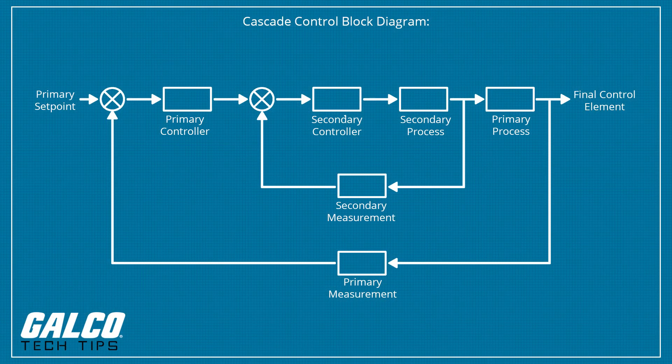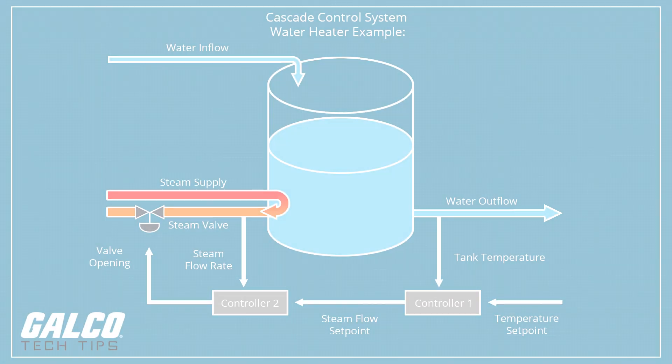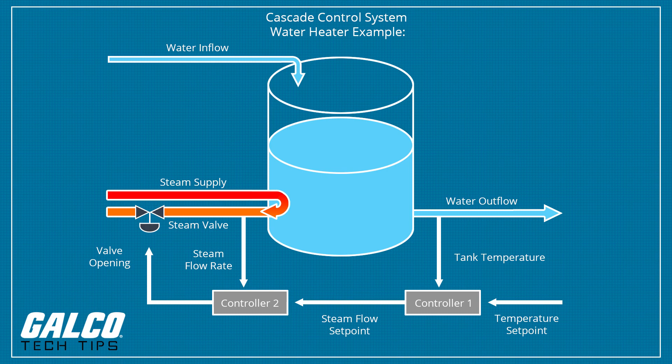However, a Cascade Control system is inherently more complex than a single-loop control system as more equipment and instruments are required, which in turn can drive up the costs of installation. Tuning Cascade controllers also becomes more difficult as the setpoint is changed and additional parameters are added. The simplest example of a Cascade control scheme involves two control loops that monitor two measurement signals to control one primary variable.